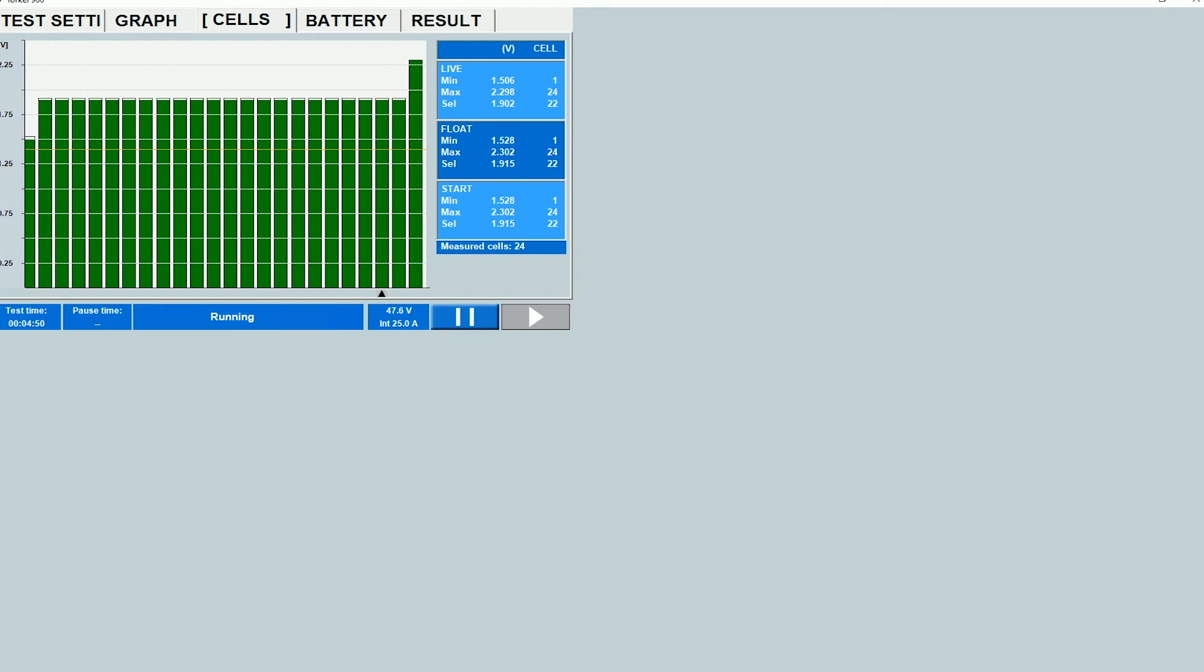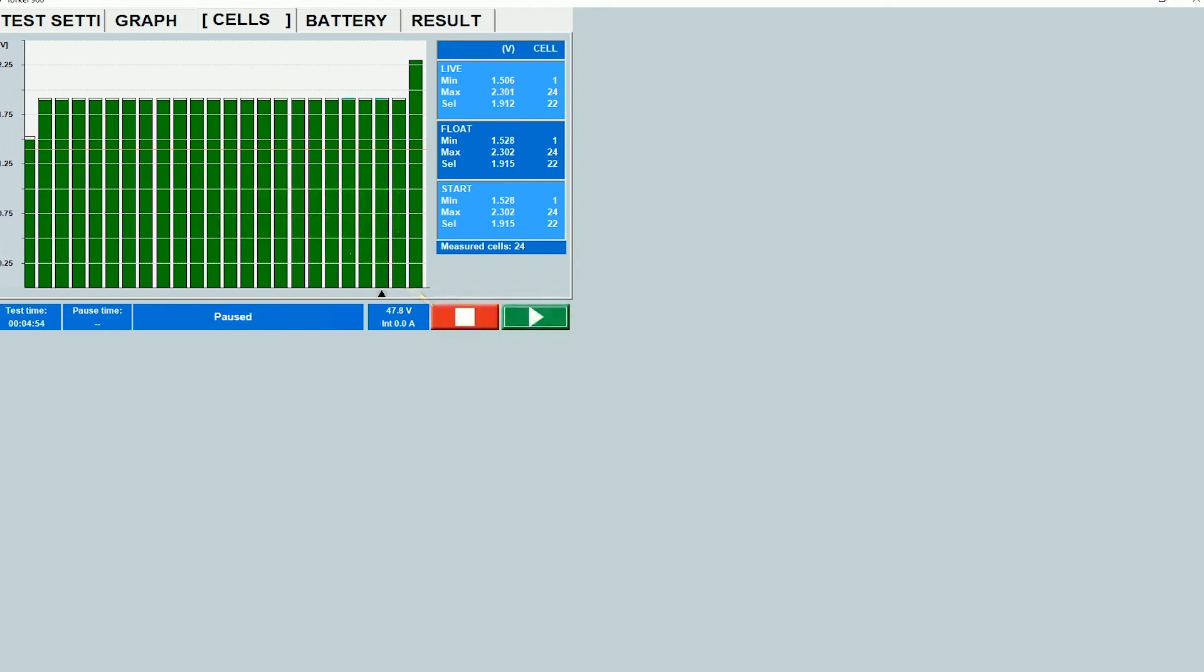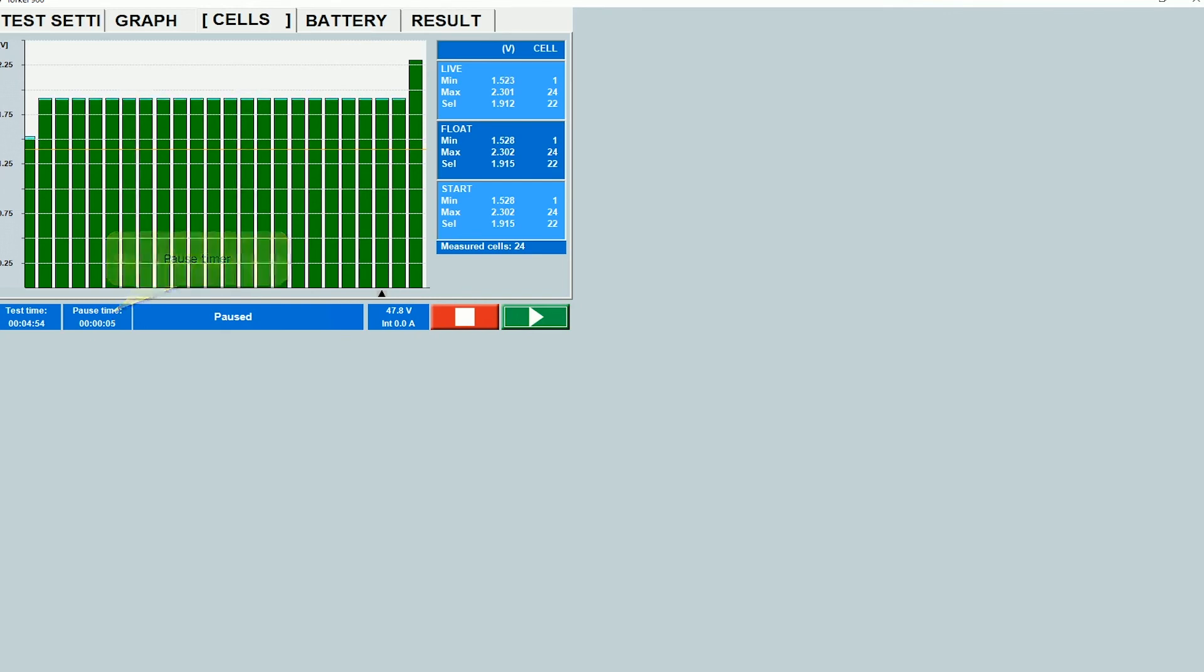So the way to pause the test is to click on the pause button here. And as soon as you hit the pause button, the pause timer starts. As I said, there's a maximum limit on the duration, and that is 6 minutes. So you want to make sure that you bypass all the bad cells and resume the test before the clock hits 6 minutes over here.